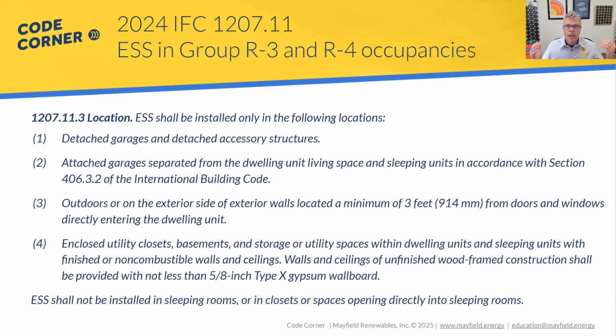So if you have ESS and you have windows or doors that are directly entering that dwelling unit, then that would be the requirement that you have to maintain that 3-foot separation from those windows and doors.